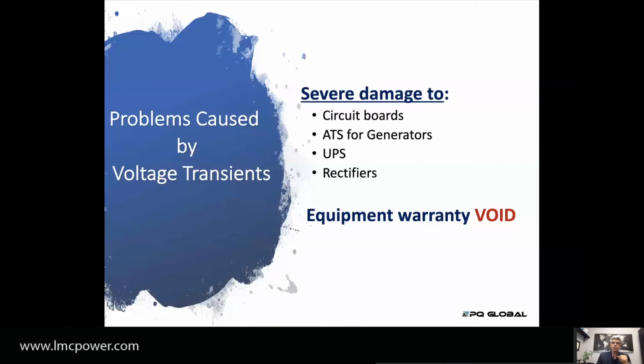So severe damage to circuit boards as we've seen, caused by voltage transients. One of the big problems we see now are ATSs, automatic transfer switches. Two days ago I was giving training to sell automatic transfer switches in North Carolina, and they see a lot of problems with the whole building depending on a generator, an emergency power system.